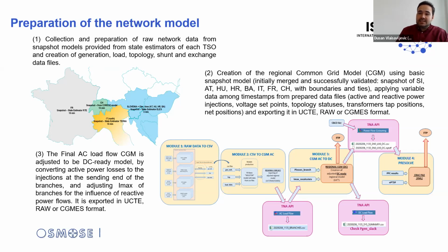In the second part, since FlexEnergy market optimization required the linearized network model, we provided a so-called linearized DC-ready model by running the AC load flow calculations on the common grid model, extracting the power losses and adding them to the injections on the sending end of the branches, and adjusting the limiting maximum current of the branches to respect the influence of reactive power flows in the further optimization process.